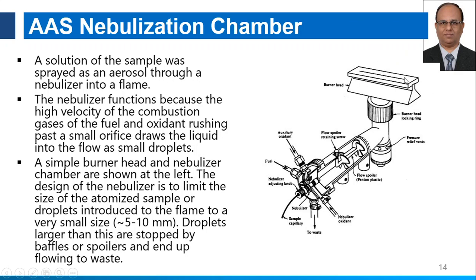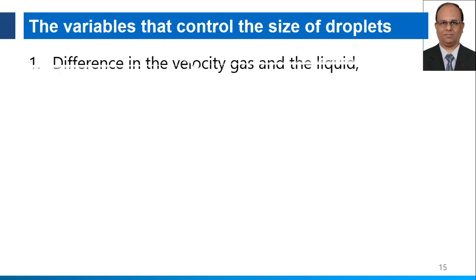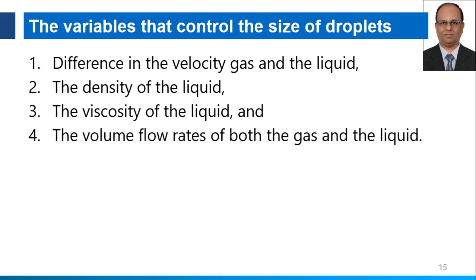The slot burner provides a bigger path length. The adjustment of flame temperature is not as critical as in the flame photometer because there is no thermal excitation here — we only need conversion of the material into atomic form, so only vaporization is essential. Variables that control droplet size are differences in the velocity of the gas and liquid, the density of the liquid, the viscosity of the liquid, and the volume flow rate of both gas and liquid.